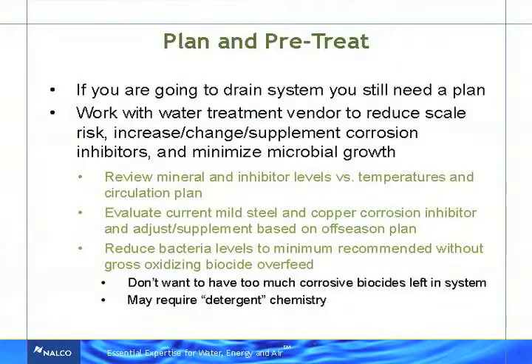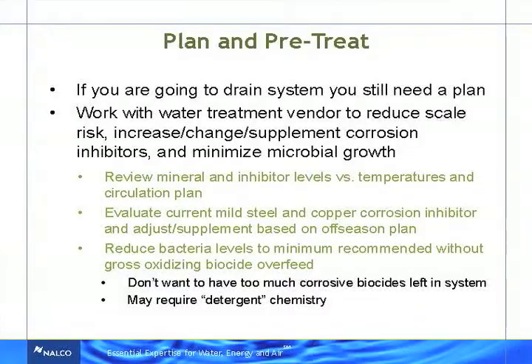So how do we prevent these issues? First way, plan and pre-treat. Anybody have boiler systems? Steam boiler systems. Before you take a boiler down, usually pre-treat, right? You plan ahead, you lay it up. People don't even think about doing that for the cooling towers a lot of times. You really should. So what you should do is, if you're going to drain the system, you still need a plan. Just because you're going to drain the system because you're not going to use it at all, you should still plan on doing some sort of pre-treatment.